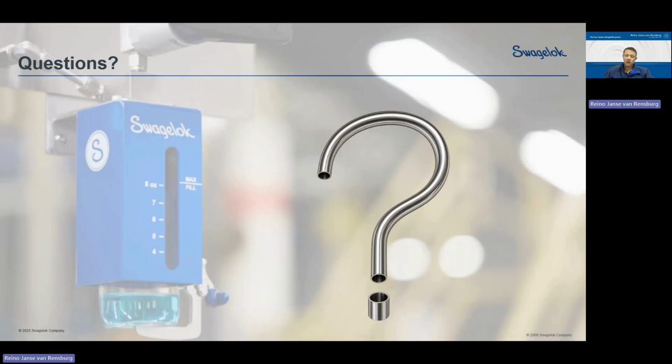A lot of these panels have multiple valves on them. If you don't know the exact orientation of these valves and how to open them, and I've seen this happen, we've done surveys on plants where I've asked a guy, please take a sample, I want to see how it works. And they literally take that media and blow it down a drain while sampling. I asked him, why is your vent valve open? And he said, no, that's just how I've been taught. So the incorrect information passes down from generation to generation, and the operators just keep doing it incorrectly. With this one valve operation, you cannot vent while sampling, it just interlocks itself. So it gets rid of all of those people problems.